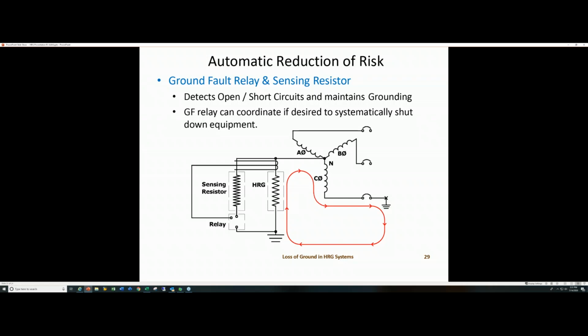There are several ways of doing it and several designs. Typically, you either put a sensing resistor in or you split the resistor, and you monitor the resistor online all the time. You have a system that's monitoring the resistance and generating an alternating high and low resistance at maybe a 1 second cycle, 2 second periodicity, so that you always know that state change in resistance, your resistor is good. That's real important to know, that your resistor is in service and it's always working. Otherwise, the unit needs to alarm.